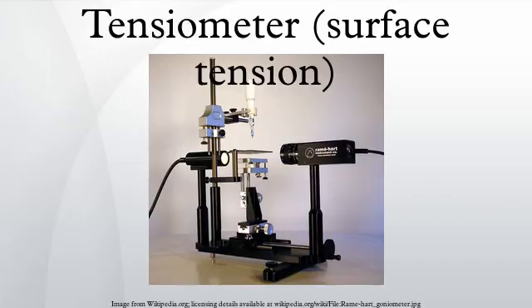Beyond this point the bubble quickly increases in size and soon bursts, tearing away from the capillary, thereby allowing a new bubble to develop at the capillary tip. It is during this process that a characteristic pressure pattern develops, which is evaluated for determining the surface tension.